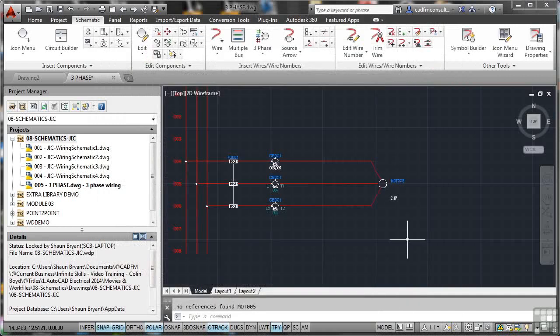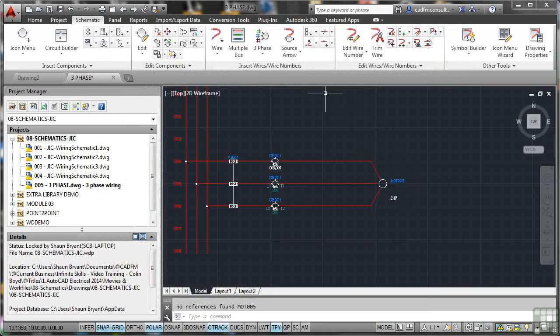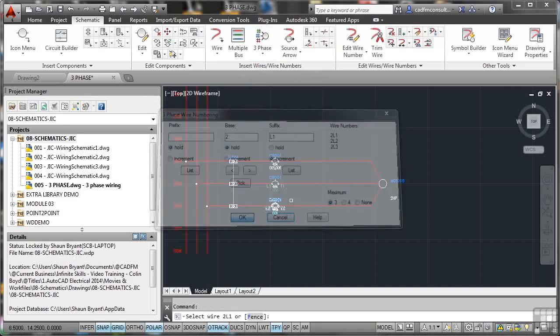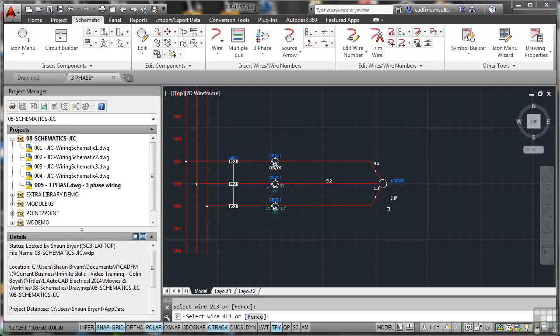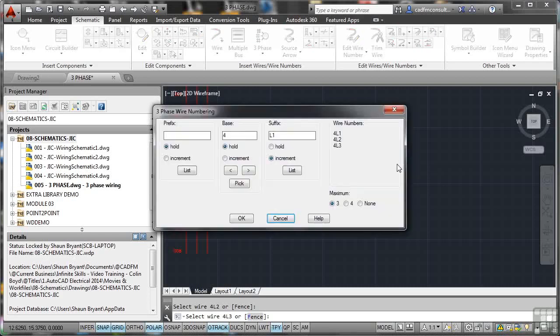So there's my motor there. So what I've got to do now is my three-phase wiring as well. So I come up here now and three-phase wiring. And what we do is we click OK and we go one and two and three. And it numbers them up for me. Now you might want to change the base number to say four by clicking there. Notice the wire numbers update. When I click OK, you'll see them update accordingly. So if I go one and two and three, you can see those update to four and then click on cancel.